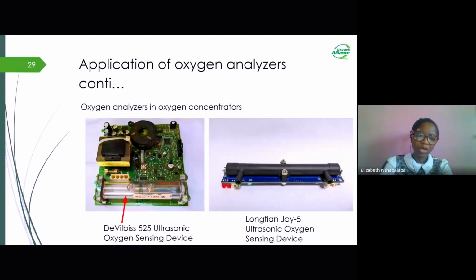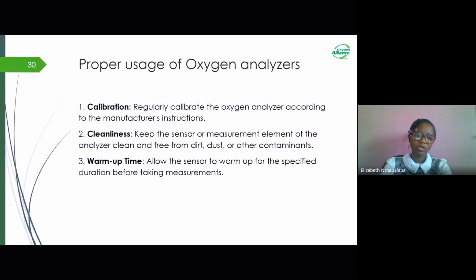Next, I will talk about some of the proper usage of oxygen analyzers that we need to consider as we use them. The first thing that we need to be aware of as we use these devices is that we should be conscious about calibration. Regularly calibrating the oxygen analyzers is important, and we should follow the manufacturer's procedure. This helps us to give the right oxygen purity to our patients.